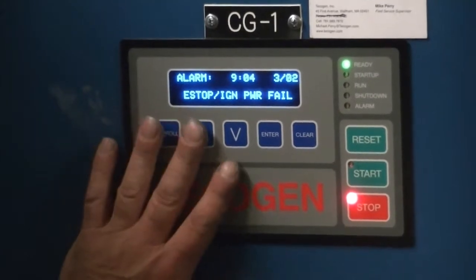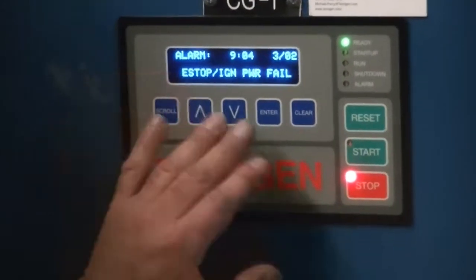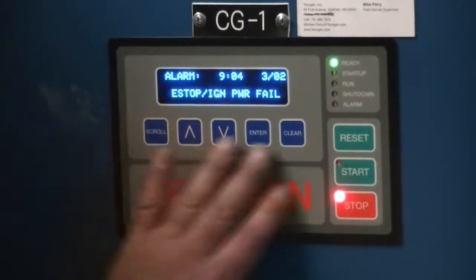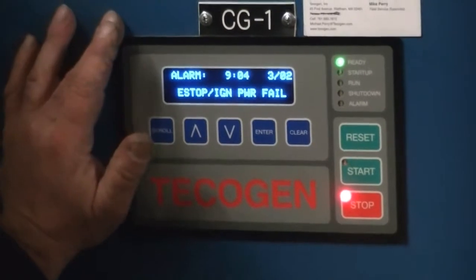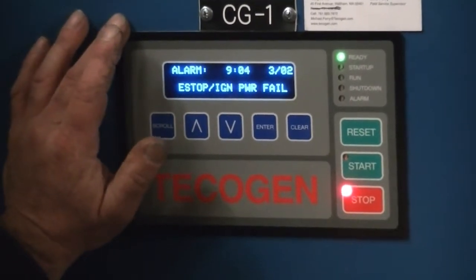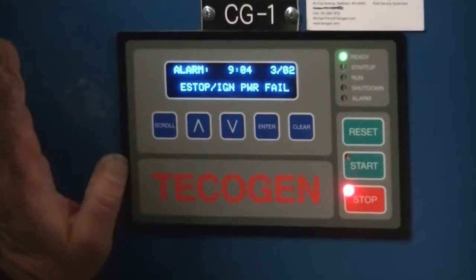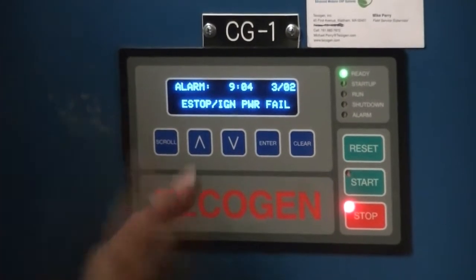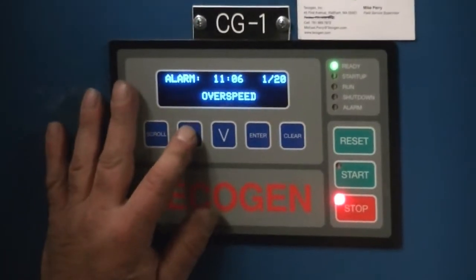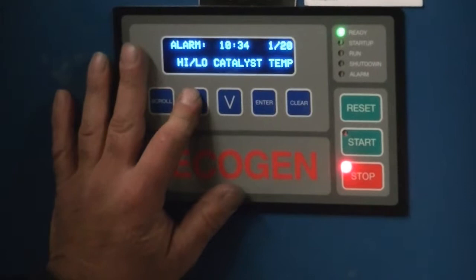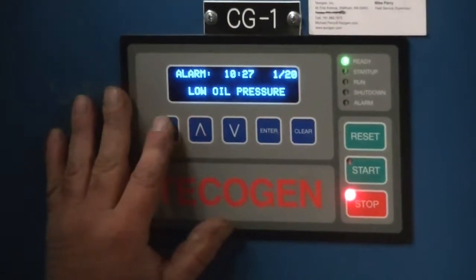The alarm page saves, I think it's 14 alarms, and tells you the time and the date it happened. If you have an alarm and you keep hitting reset, you're going to wipe all those alarms out. If you only have one alarm, it's going to be all the same date, same time. So you're best off just calling me and I can come over and check it out. These are all the alarms we tested in my startup.